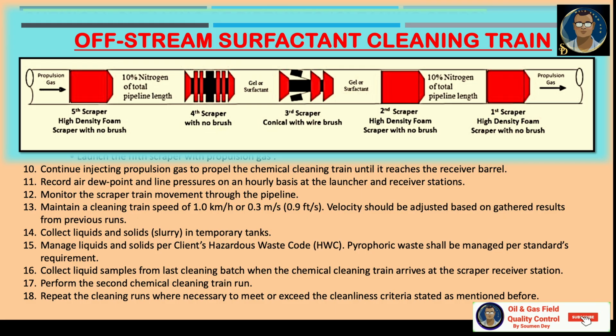Collect liquid samples from the last cleaning batch when the chemical cleaning train arrives at the scraper receiver station. Perform the second chemical cleaning train run. Repeat the cleaning runs where necessary to exceed the cleanliness acceptance criteria which I have mentioned before.